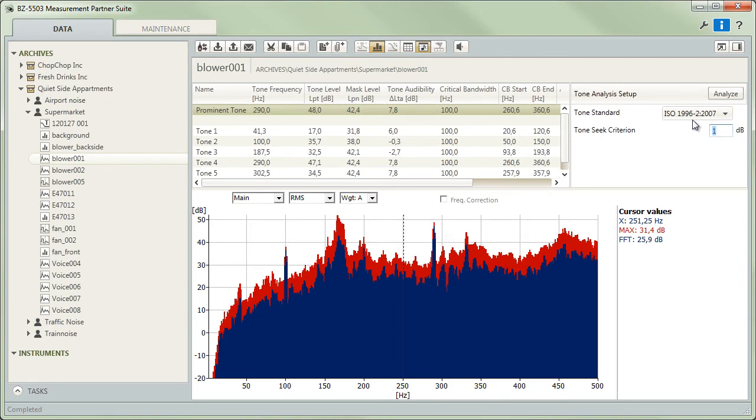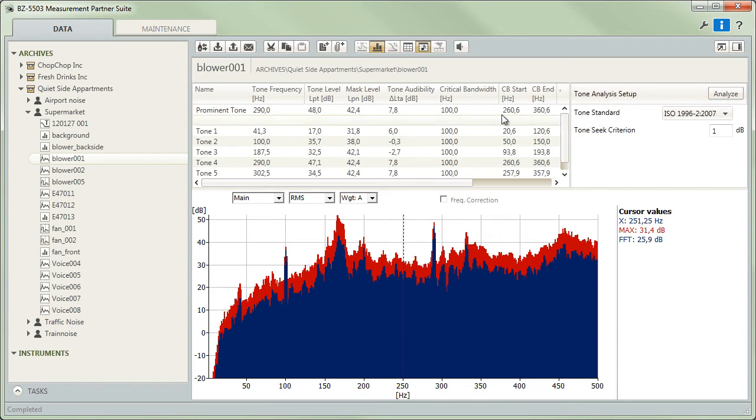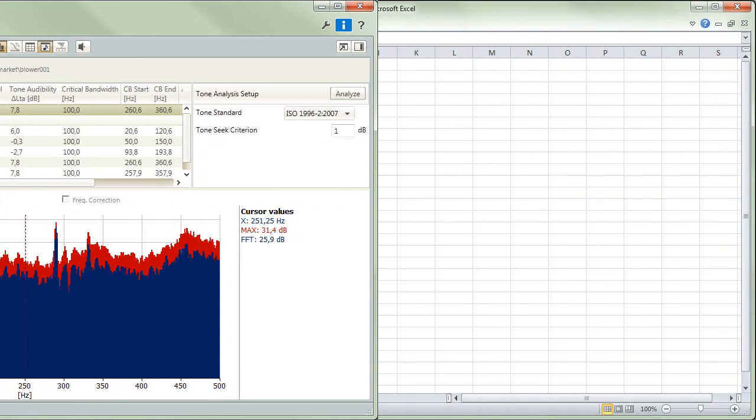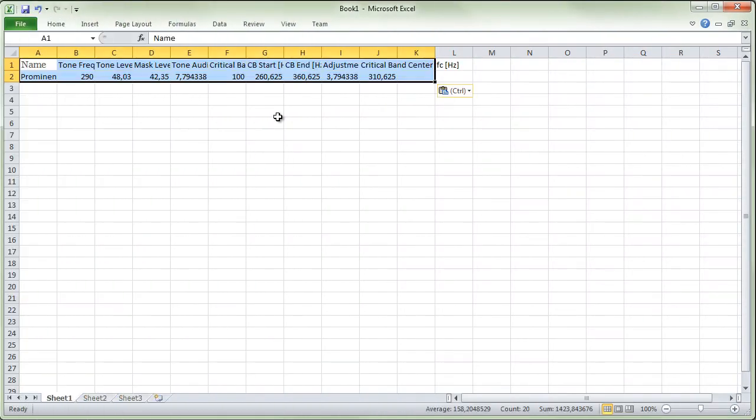All peaks that fulfil the criteria of a tonal component will be listed in the table, and Measurement Partner will indicate the most prominent. You can then just select, right click and copy this row in the table and paste the results into a report.